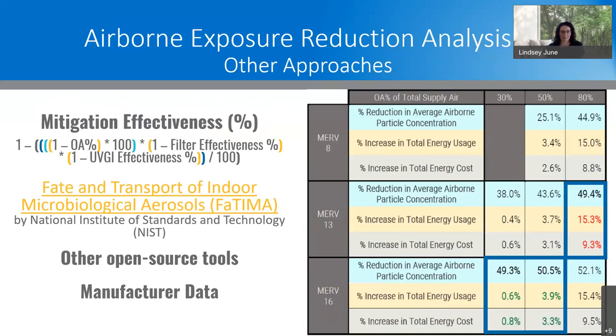So on the right of the slide here, you can see how Siska used the output from the FATIMA tool to quantify the percent reduction in airborne particle concentration of all combinations of outdoor air at 30%, 50%, and 80%, and with MERV filter ratings of 8, 13, and 16. So they created this matrix showing the percent reduction in airborne particle concentration, along with separately calculated percent increase in total energy use and total energy costs in relation to the baseline condition of the building, which is the grayed out box there, representing MERV 8 with 30% outdoor air.